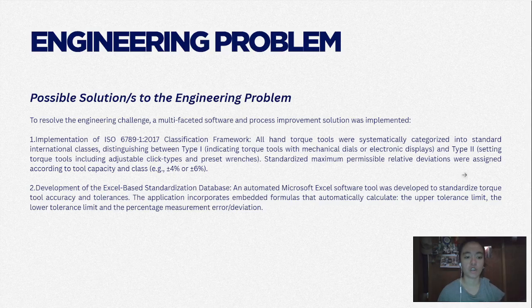ISO 6789-1:2017 classification framework. So, all hand torque tools are systematically categorized into standard international classes, distinguished between type 1 and type 2, for tools including adjustable, click types, and preset wrenches, with standardized maximum permissible relative deviation assigned according to tool capacity. And for the development of the Excel-based standardization database, an automated Microsoft Excel software tool was developed to standardize tool accuracy and tolerance, and the application incorporates embedded formulas that automatically calculate the upper tolerance limit and the lower tolerance limit in the percentage measurement error given.